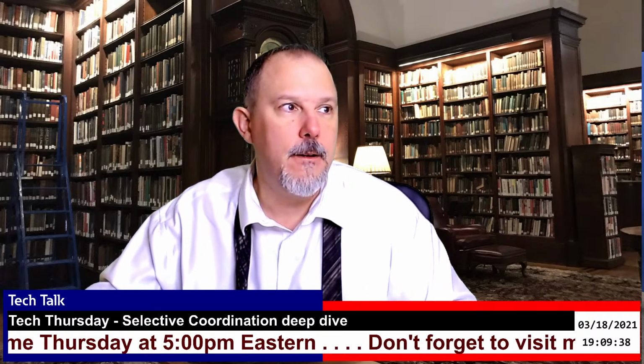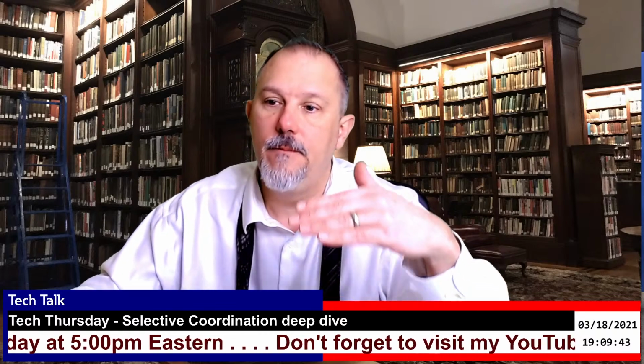All right, that's all we can think of for now. So it is 7:09. I went 9 minutes over my little 2 hour, and we didn't talk about arc flash reduction in light of selectively coordinating, but for this system, we did run the arc flash studies. And there are a couple different ways because we are going to electronic trip units. You can use the arc reduction maintenance switch. Yeah. Boom. We're done, right?